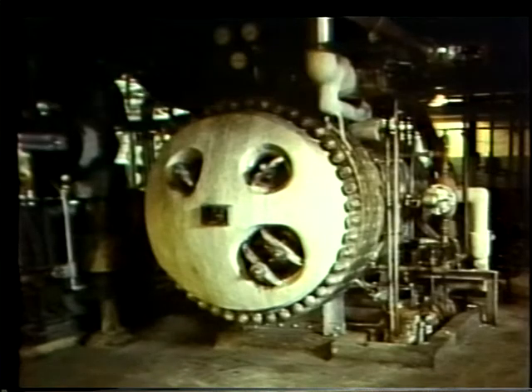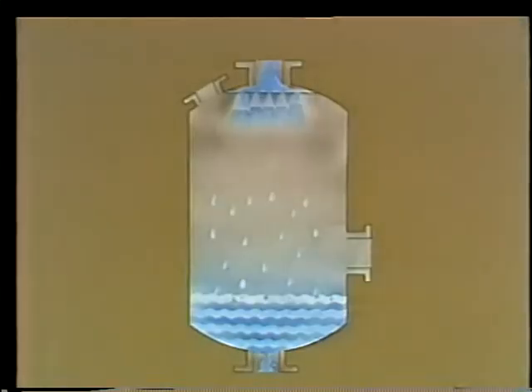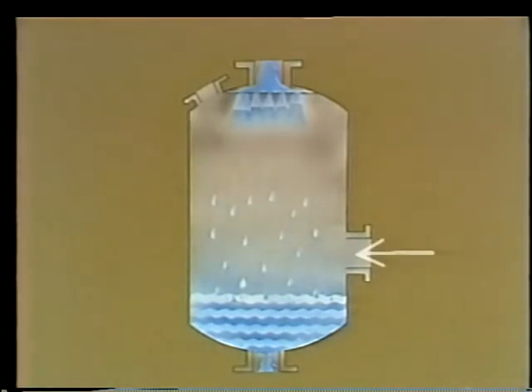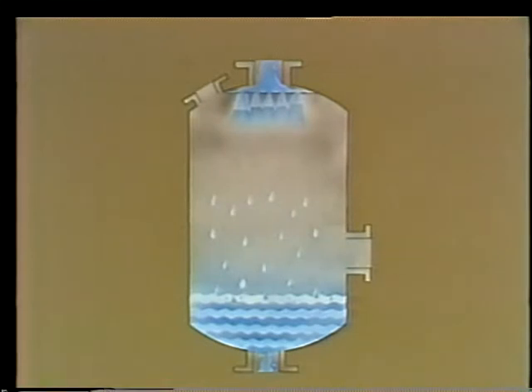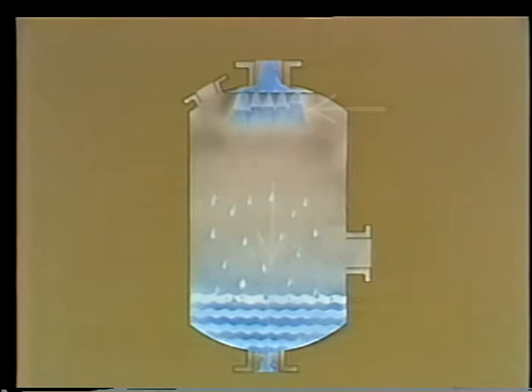Although condensers and shell and tube heat exchangers are similar in many ways, they usually don't look alike. Direct contact heat exchangers on the other hand may look quite like a shell and tube exchanger but don't share many other similarities. The direct contact exchanger is a heater used to heat feed water for a boiler. It condenses the inlet steam back to water which goes back into the feed water system. This type of heat exchanger is sometimes called a de-aerating heater or a cascading heater because the incoming feed water cascades down through the condensing steam and falls down to an outlet or a storage tank.